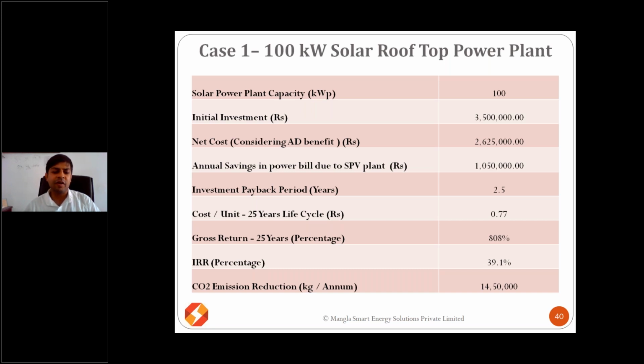I mentioned we need to consider the base load and select the plant appropriately, but the maximum output from a solar power plant is about 80% of its rated capacity. So a 100 kilowatt plant will typically have a maximum output of around 80 to 82 kilowatts, not more. That's why we chose a 100 kilowatt plant when their base load was around 90 kilowatts.